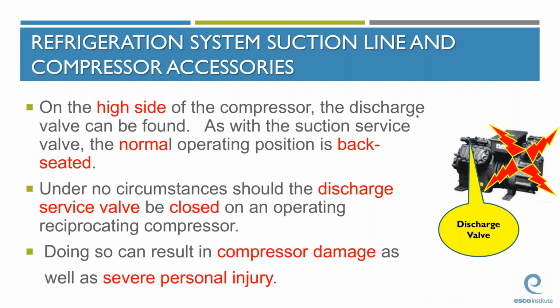On semi-hermetic compressors, another service valve can be found, and this is the discharge service valve. As with the suction and liquid service valves, the normal operating position of this valve is back-seated. Under no circumstances should the discharge valve be closed or front-seated on an operating reciprocating compressor. Front-seating this valve can result in major compressor damage as well as severe personal injury. It's important that your students are aware of the dangers associated with improper valve positioning. You also need to let them know that if they have any doubt, they should ask for assistance before energizing the system.